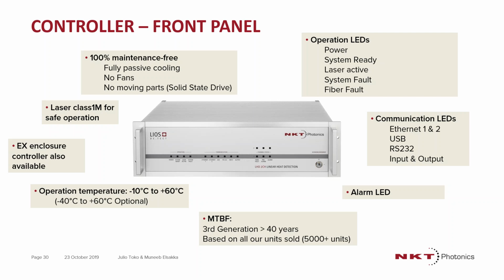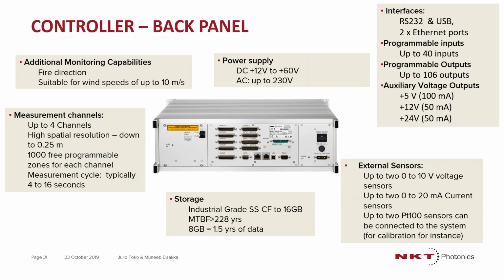In terms of the way we design the system, because we are using lasers, we can design the system based on different applications. So if you want explosion-proof areas, we control the laser in such a way that it's not interfering with anything if somebody accidentally breaks the cable. In terms of communication systems as well, we can look at the back panel. It's very configurable. If you have a project of 100 zones, we can deliver 100 output relays. If you have a project of 10 zones, you can deliver only 10 output relays.